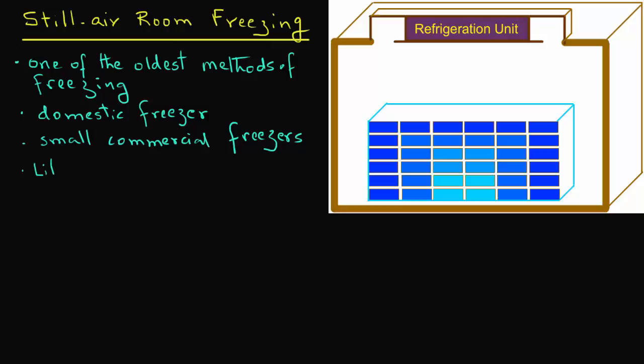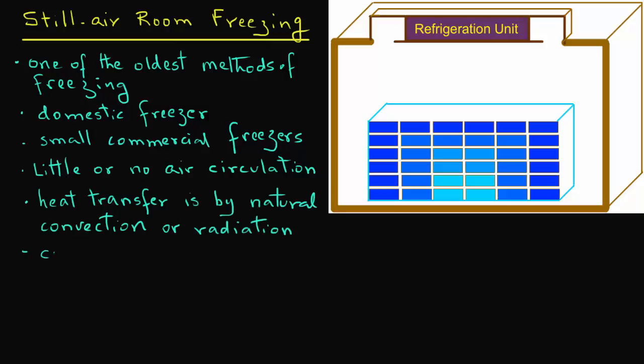There are two issues here. One is that there is little or no air circulation, and heat transfer is by natural convection or radiation. The convective heat transfer coefficient in such rooms is between 5 and 10 watts per square meter Kelvin.